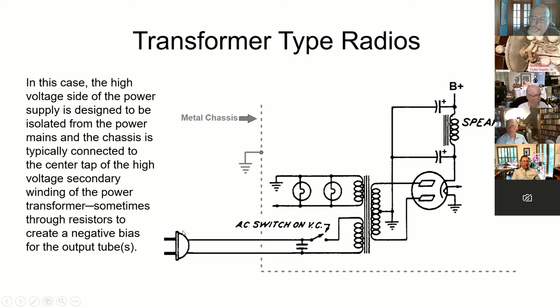Now, if that shorts, it's not great, but hopefully it would trip the circuit breaker, because there would be an unlimited amount of current flowing between these two lines. The high voltage side, again, is isolated from the power mains. So your ground here is not necessarily going to be hot.